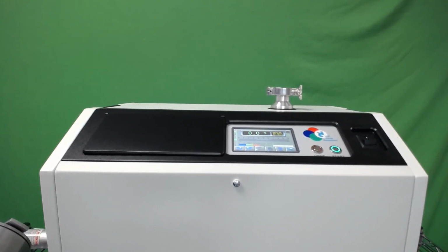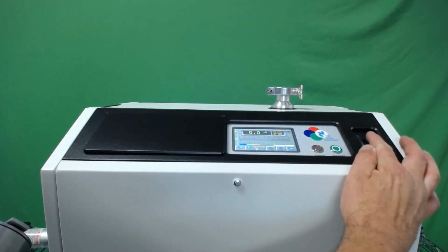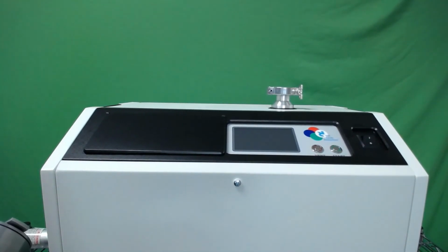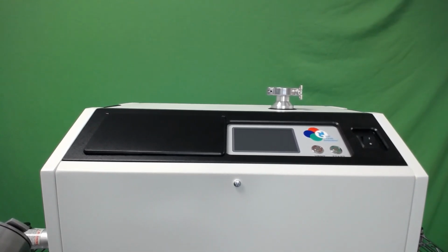To shut the machine down, you simply take the power switch and turn it to the down position or the 0 position. The machine will automatically turn the filaments off, turn the pumping package off, and it's ideal, even though the machine is no longer powered up, to wait approximately 5 minutes for the turbo that's running at approximately 80,000 rotations a minute to stop rotating before the unit is moved.